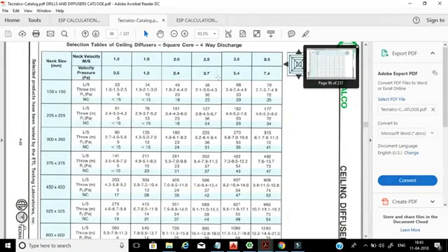The noise criteria here is 18, which is just okay — it means not very comfortable. Less than 15 is a much better noise criteria. So what is the friction loss for this particular grill? Here you can see the velocity pressure is 3.7 Pascal. Grills and diffusers data we can enter directly in our Excel sheet.